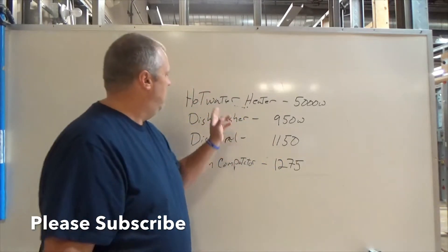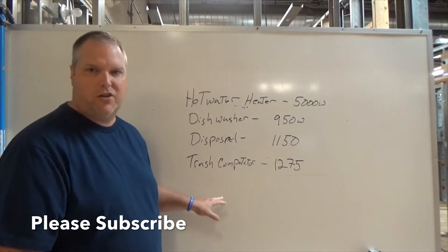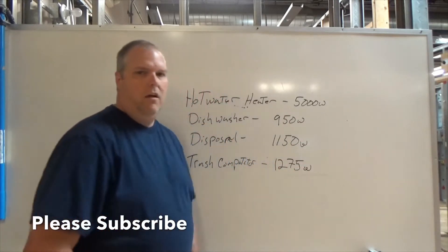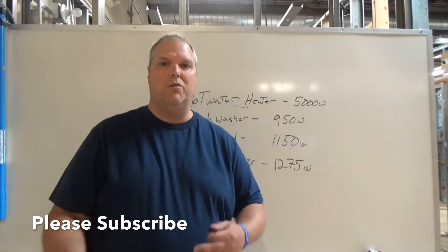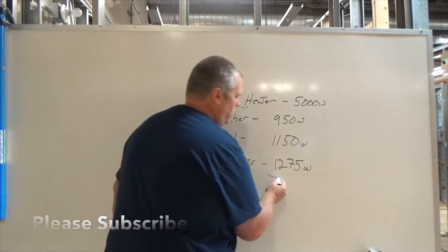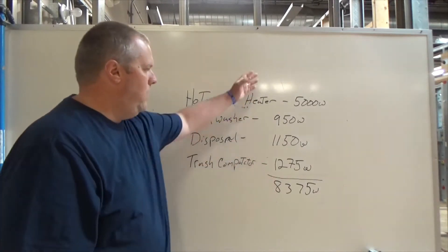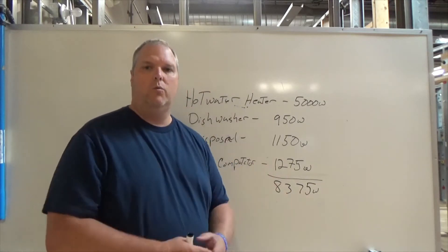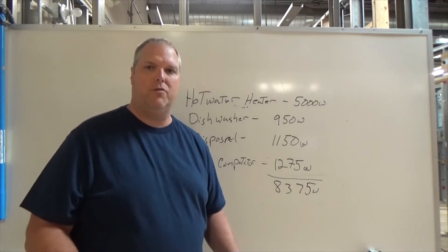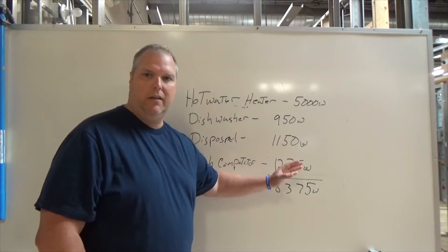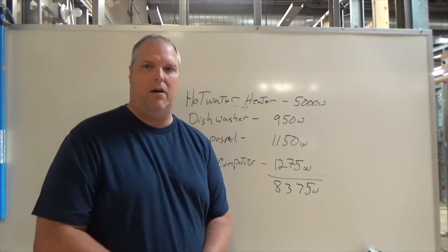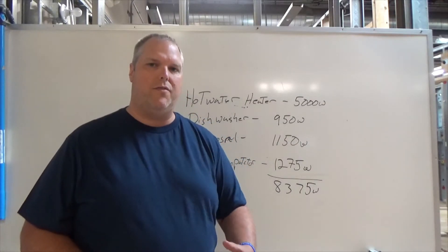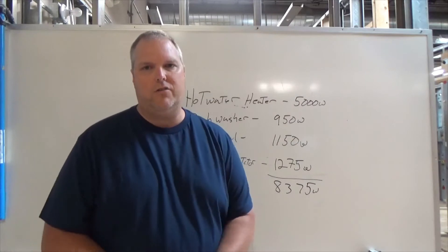On the board I have a hot water heater, a dishwasher, a disposal, and a trash compactor with their wattages listed. When sizing fixed appliances, we add them together. As you can see on the board, when we add these together we get 8,375. When sizing them we're taking them at 100 percent and doing our Ohm's law calculation.